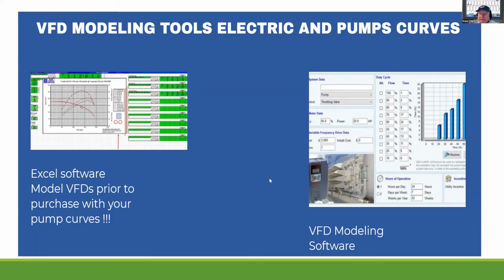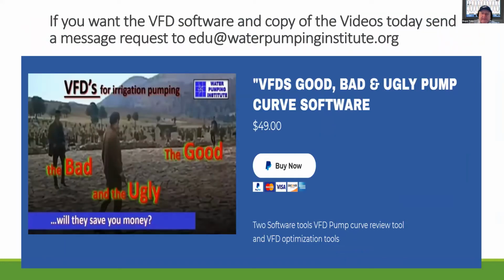I also will send you a software tool that allows you to put in the data from here, when you're going to use it and at what time points, and then model the VFD to see what you're truly going to save in energy. So you're putting the proper data from the pump into the VFD software that comes from the VFD manufacturer, and you're ultimately going to see a much better reality of the value of savings.